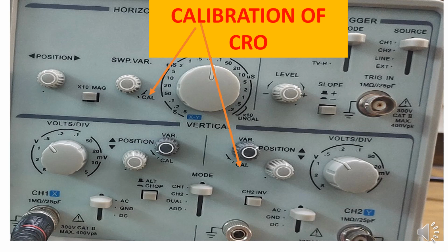So these are the calibration points. Don't touch these calibration points. Once you have calibrated the CRO, then don't touch these points. If you change or rotate them, you have to repeat the whole experiment again. You have to set the frequency first, so that the measurement error is less.